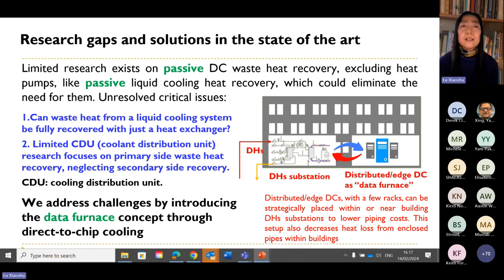Okay. Two critical research issues can be summarized. First, can this heat from liquid cooling system be fully recovered with just a heat exchanger without a heat pump? Second, limited CDU research has focused on primary side waste heat recovery only. Secondary side recovery has been completely neglected. CDU here represents coolant distribution unit or cooling distribution unit that distributes water or coolant in the liquid cooling system.